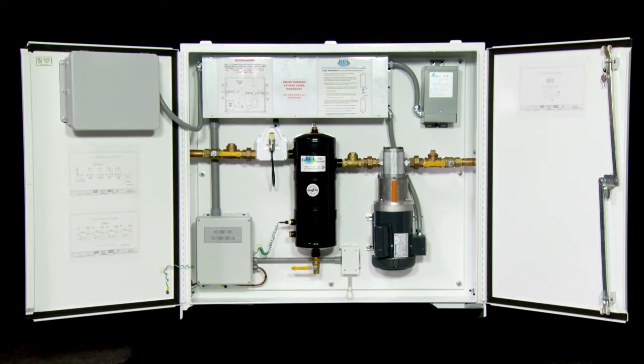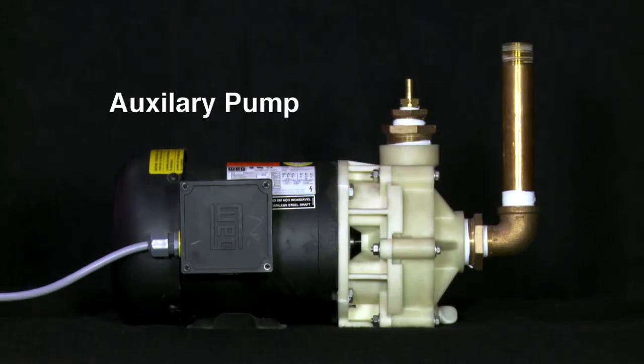Remember, the FRS is not designed to remove bulk water from the diesel fuel tanks, as this could lead to pump failure. Instead, an auxiliary pump is recommended for bulk water removal.